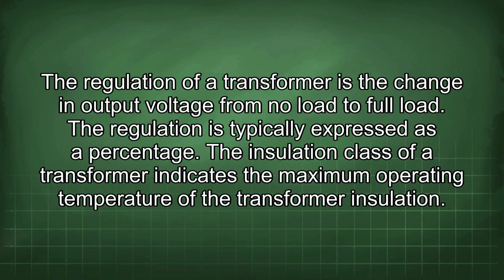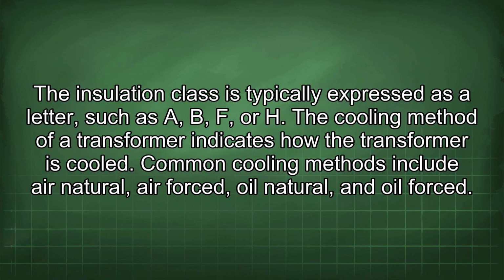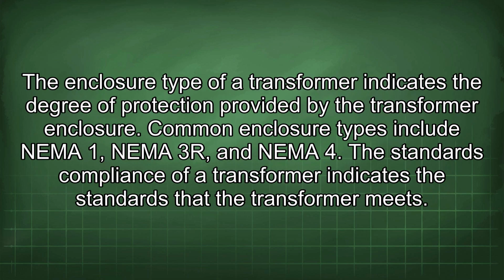The insulation class of a transformer indicates the maximum operating temperature of the transformer insulation. The insulation class is typically expressed as a letter such as A, B, F, or H. The cooling method of a transformer indicates how the transformer is cooled. Common cooling methods include air natural, air forced, oil natural, and oil forced. The enclosure type of a transformer indicates the degree of protection provided by the transformer enclosure. Common enclosure types include NEMA 1, NEMA 3R, and NEMA 4.